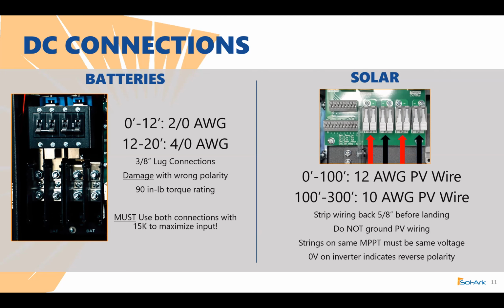When connecting that wire, you want to make sure to strip that wiring back about 5/8 of an inch before landing it. Do not ground to PV like you used to. For those old school guys, we don't have a positive or negative grounding for those PV lines anymore. It's not very common. If you have two strings on the same MPPT, please keep them equal in a parallel setting. It will affect the voltage if you have an unequal amount of strings, a string of 6 and a string of 8 on MPPT1. And if you do accidentally reverse polarity on the MPPT, you'll just get 0 volts on the inverter. It won't damage it, but it will tell you that you swapped it.